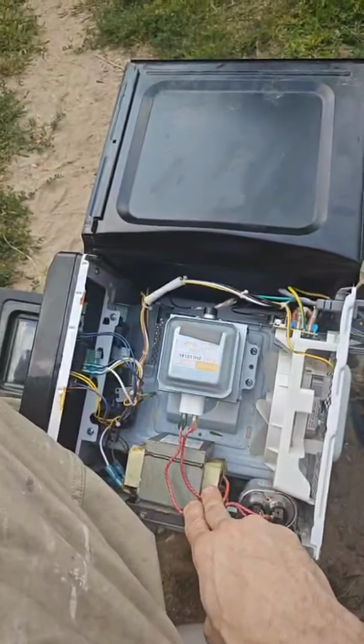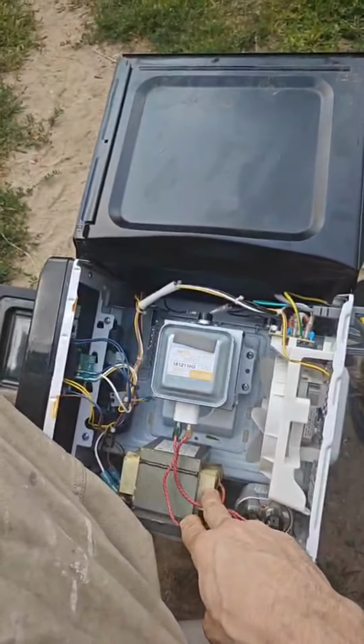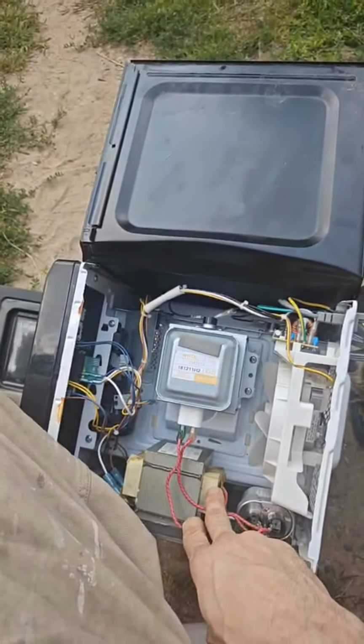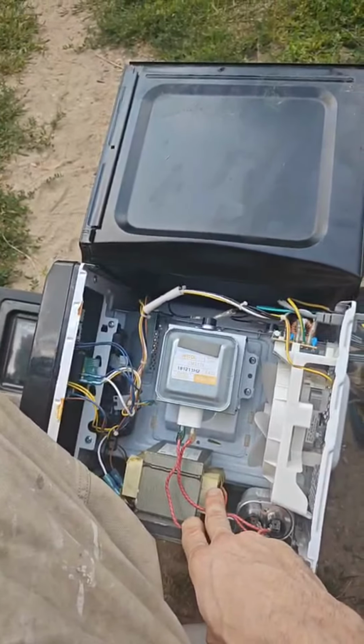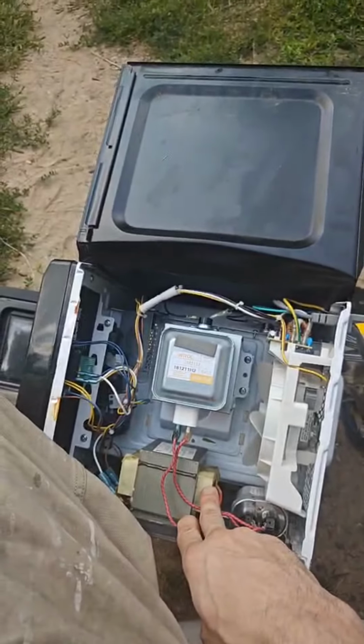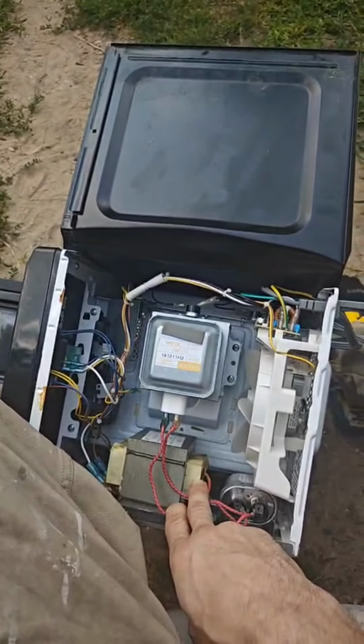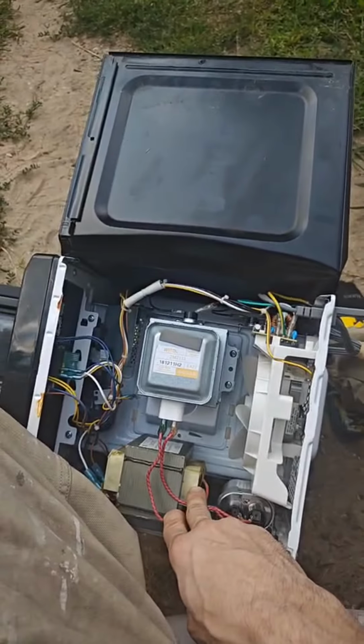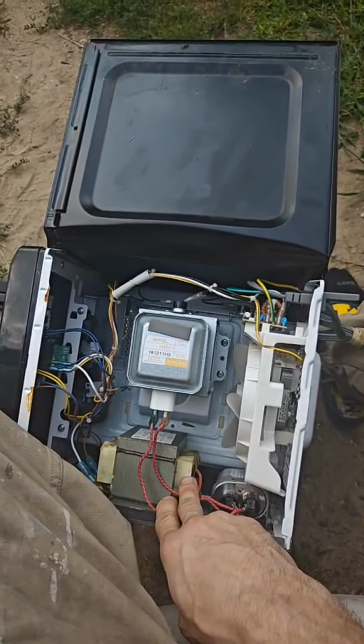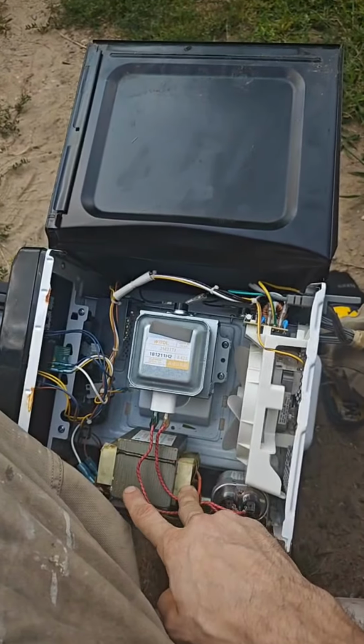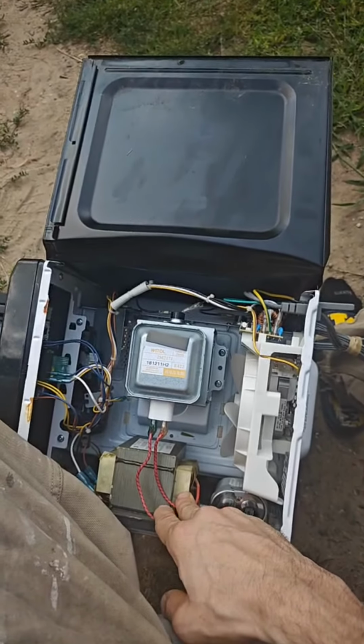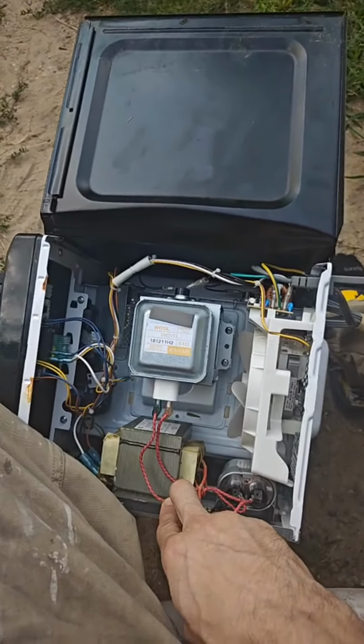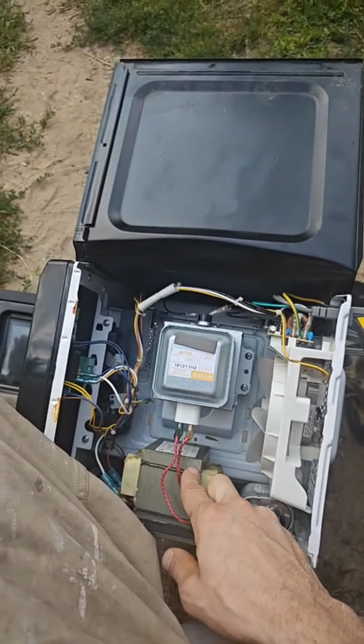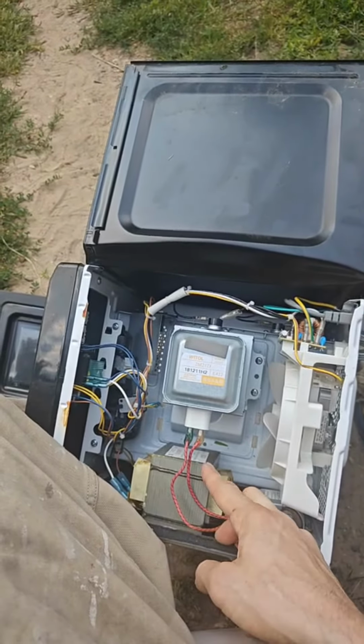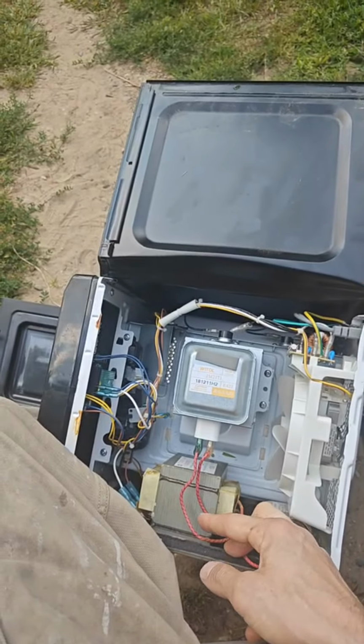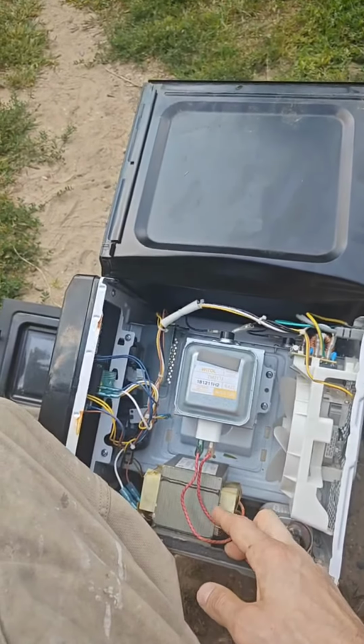But if you cut the secondary off and rewrap it, usually about 20 times or so, you get about 1.2 volts per turn approximately, one full winding around the core. It depends on the transformer wrap, but usually that's what it is, around a volt per wrap. So if I wrap this 24 times or so, I'd be about, rounding down, say 24 volts.